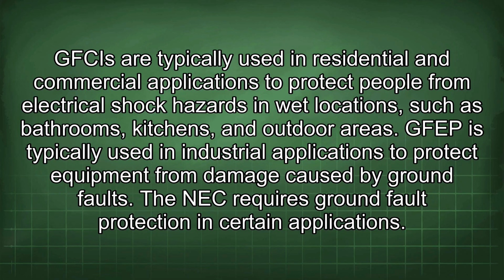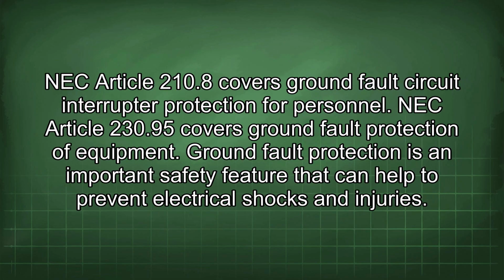GFEP is typically used in industrial applications to protect equipment from damage caused by ground faults. The NEC requires ground fault protection in certain applications. NEC Article 210.8 covers ground fault circuit interrupter protection for personnel. NEC Article 230.95 covers ground fault protection of equipment. Ground fault protection is an important safety feature that can help to prevent electrical shocks and injuries.